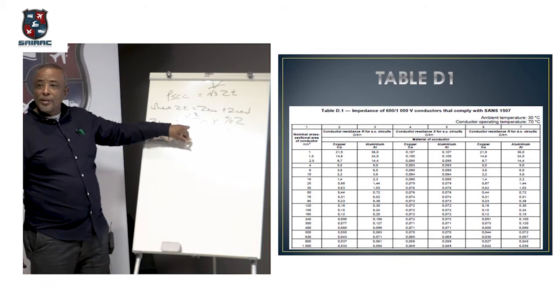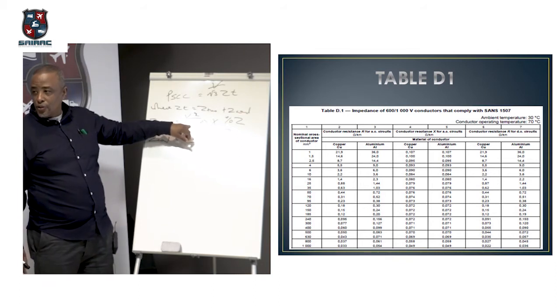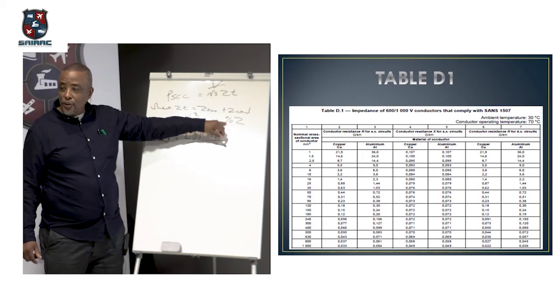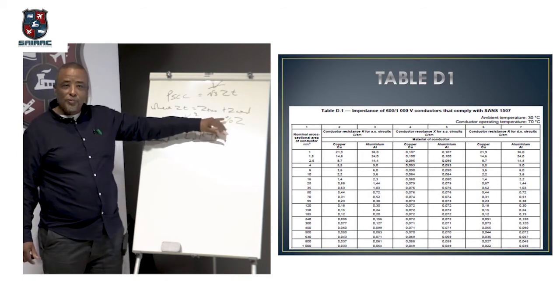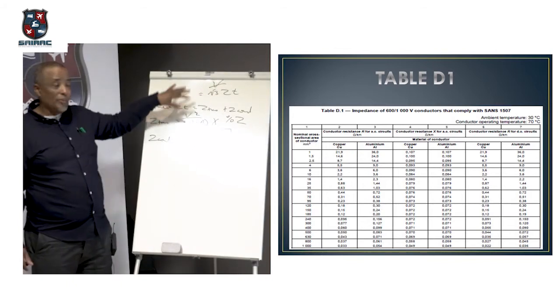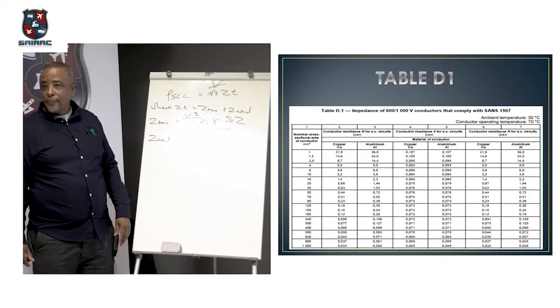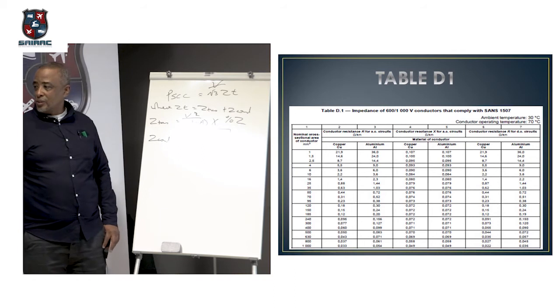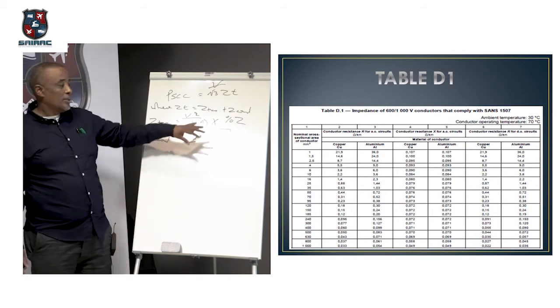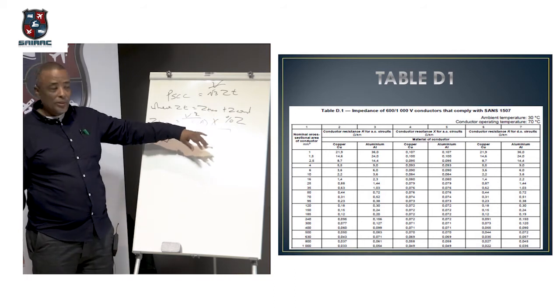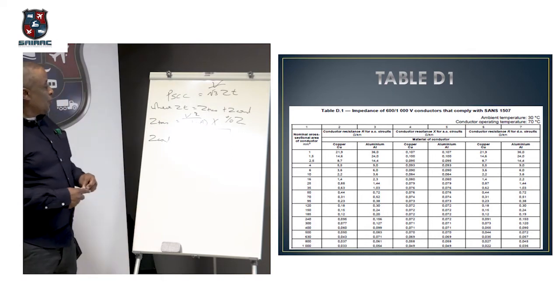This kVA rating is basically on the transformer. 315 kVA is the normal size that's used. This information will also be on the transformer. The percentage impedance will also be on the transformer. So everything is given to you. You must just memorize the formula. Okay, if you forget also, if you don't work with it every day, the formula is in the book as well. Okay, that's very important.